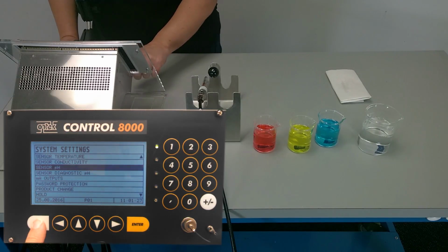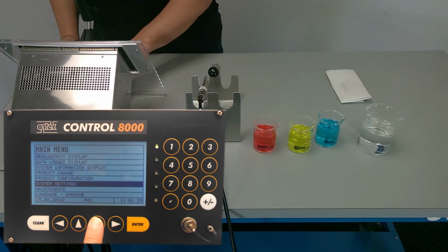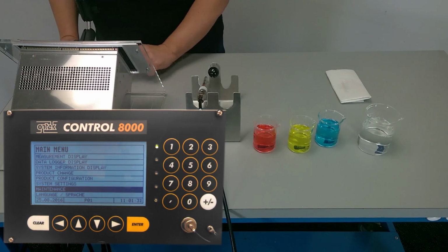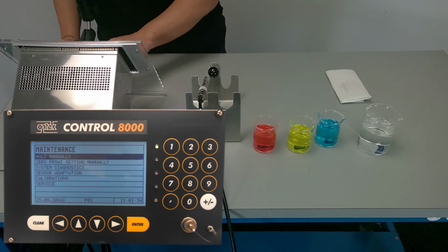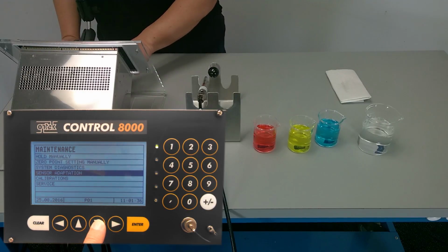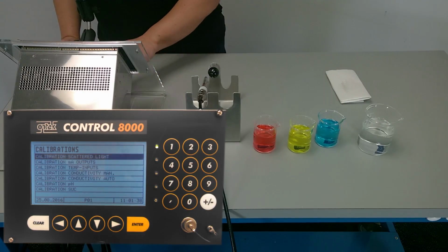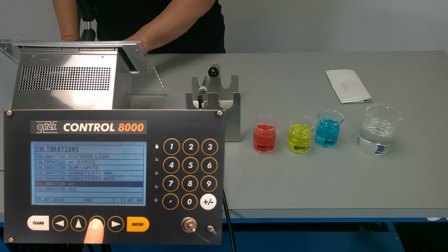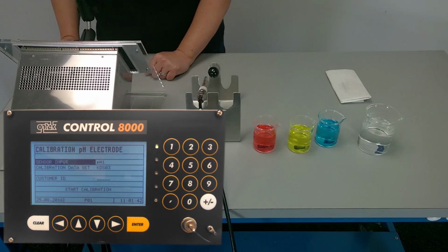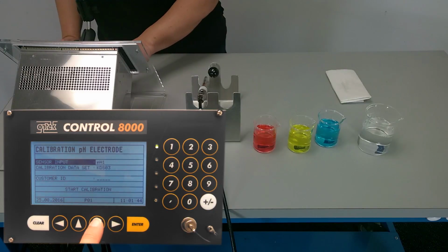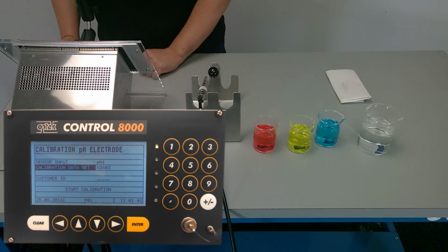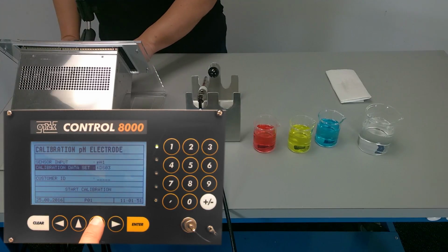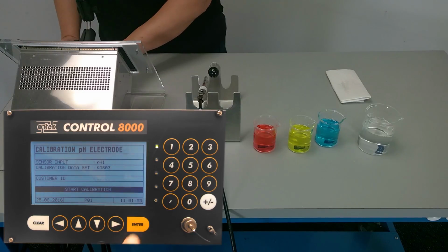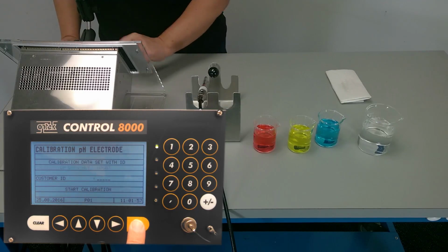In order to start the pH calibration, you are going to use the maintenance screen from the main menu. Hit Enter. You're going to scroll down to Calibrations, hit Enter, and scroll to Calibration pH and hit Enter. So from here, we will keep it on pH1. The calibration data set, the converter will hold up to 8 of them, so you can select whichever one you want. You can put in a customer ID. It's not necessary. Scroll to Start Calibration and hit Enter.